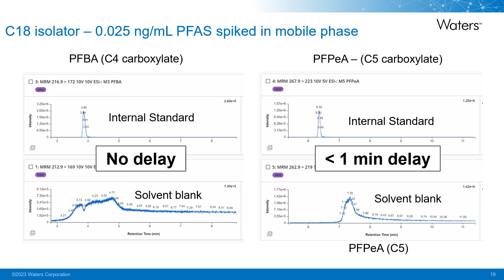The chromatograms on the top are just a retention time marker using an internal standard for those particular compounds. So this is the retention time we expect these compounds to elute at. If we shift to looking at PFBA, the C4 carboxylate, which is a common contaminant in at least my mobile phase and my solvents, what is eluting on the solvent blank is now smearing out, starting before the peak is actually eluting off the column to a time period after, engulfing that analytical retention time of our compound. And this is going to severely impact the analysis of these PFAS compounds.